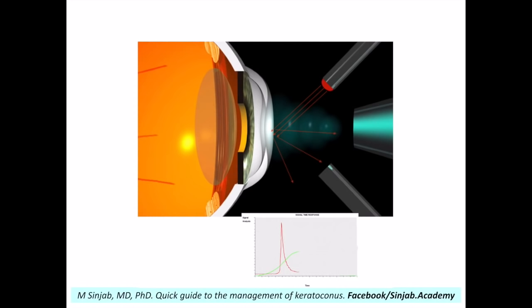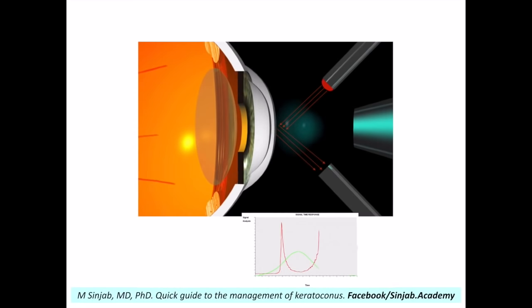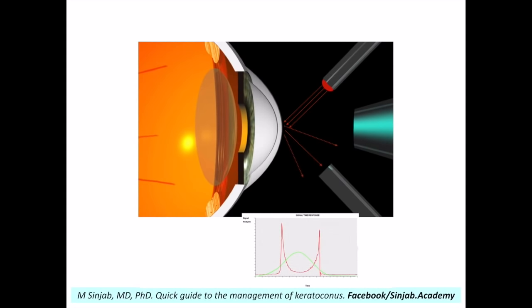The cornea continues to go inward and takes a concave shape, so the reflected rays diverge again and the light intensity measured by the receptor falls. Then the cornea starts to recover its primary shape, returns to the flat position, and the reflected light rays again travel in a parallel path, giving a maximum intensity and drawing the second peak of the ORA waveform. When the cornea finally returns to its convex primary position, the rays are reflected divergently and the intensity falls again.